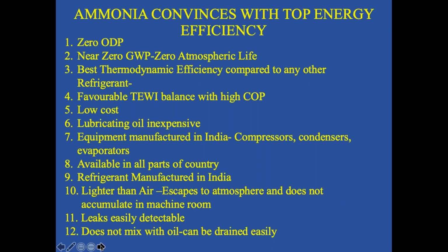It is very low cost. The man-made refrigerants cost 3,000 rupees a kg, 4,000 rupees a kg. Ammonia costs only 60 to 70 rupees a kg. Lubricating oil is a mineral oil, very, very inexpensive. We don't have to use PAG oils or POE oils. All the equipment is manufactured in India: compressors, condensers, evaporators, etc. The equipment parts are available all over the country. The refrigerant is available all over the country, right from Kashmir to Kanyakumari.